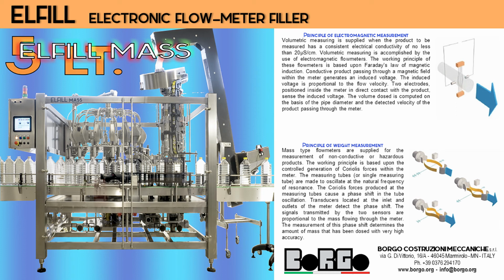Conductive product passing through a magnetic field within the meter generates an induced voltage. The induced voltage is proportional to the flow velocity. Two electrodes, positioned inside the meter in direct contact with the product, sense the induced voltage. The volume dosed is computed on the basis of the pipe diameter and the detected velocity of the product passing through the meter. Principle of weight measurement.